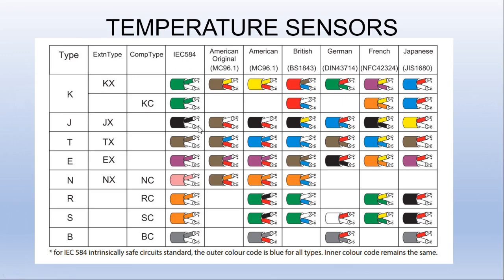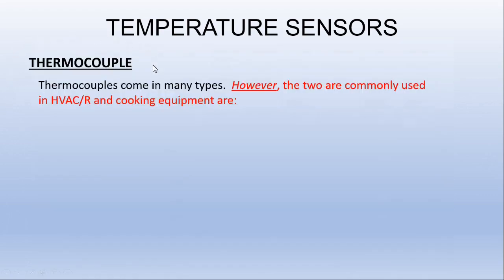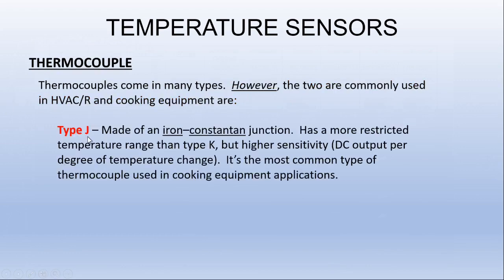This chart basically will just confuse you. You're rarely going to be able to use it to translate what type of thermocouple you're looking at. Usually you would need to consult with the manufacturer to determine what type of thermocouple they put in it. So, thermocouples come in many types. However, the two most commonly used in HVACR and cooking equipment are the type J.